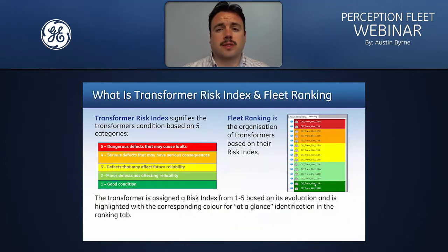Within Perception Fleet, when data is received from the monitor, our intelligent algorithms evaluate the data and assign a risk index to the transformer. You can see the categorization in the left-hand table. We have a risk index of 1, which indicates that the transformer is in good condition. 2 shows that there are minor defects not affecting reliability. 3 shows defects that may affect future reliability. 4 indicates that there are serious defects that may have serious consequences. And 5 shows that the asset has dangerous defects that may cause faults.